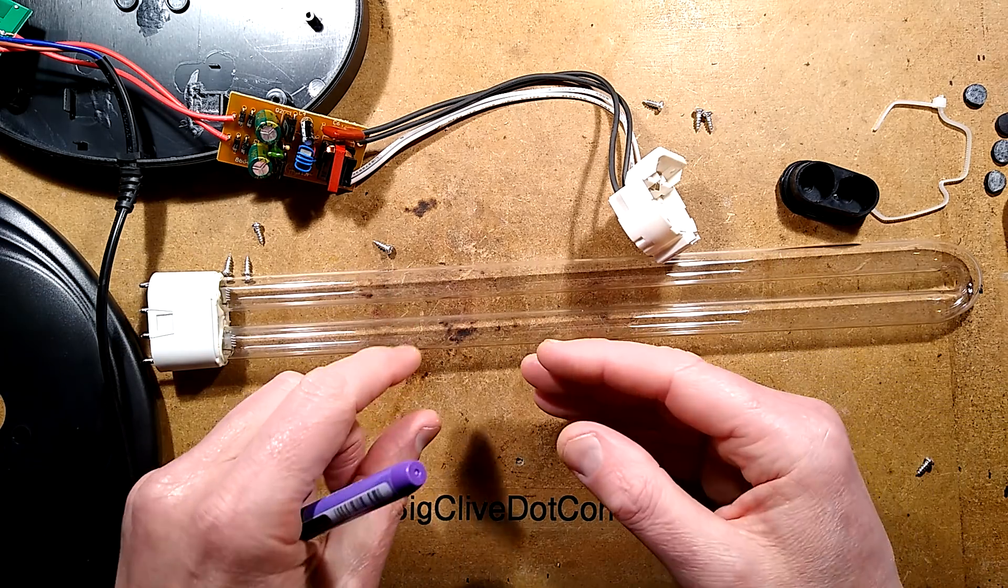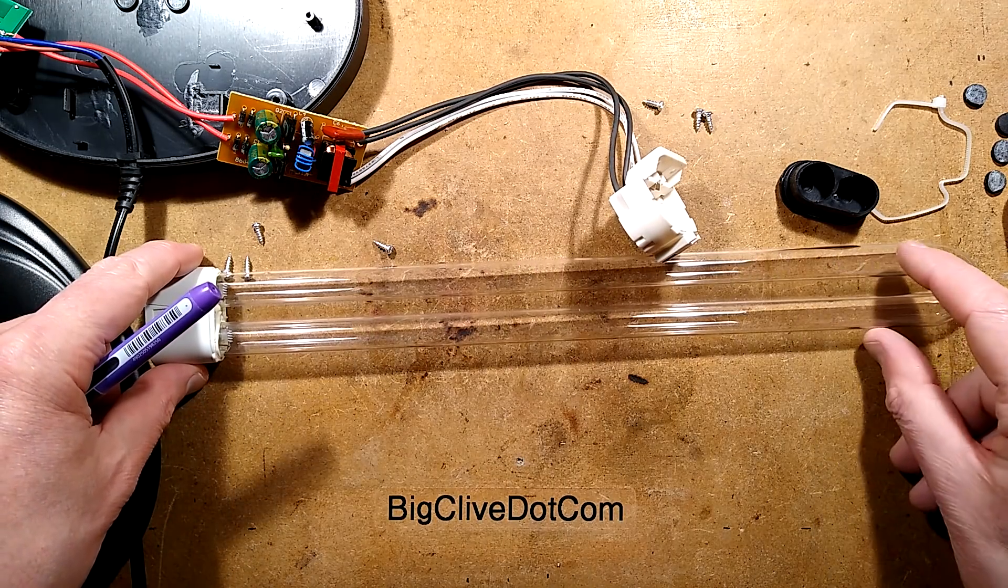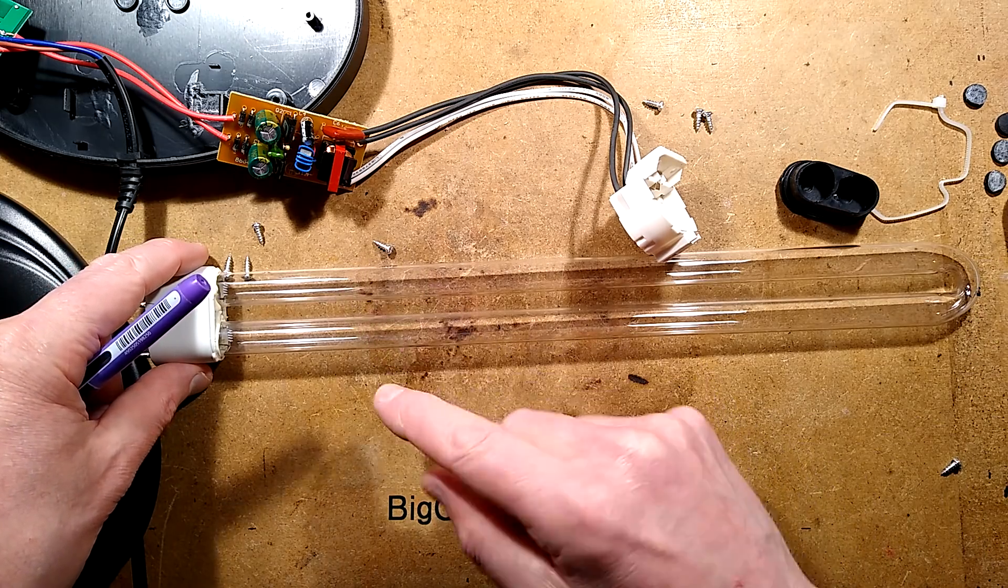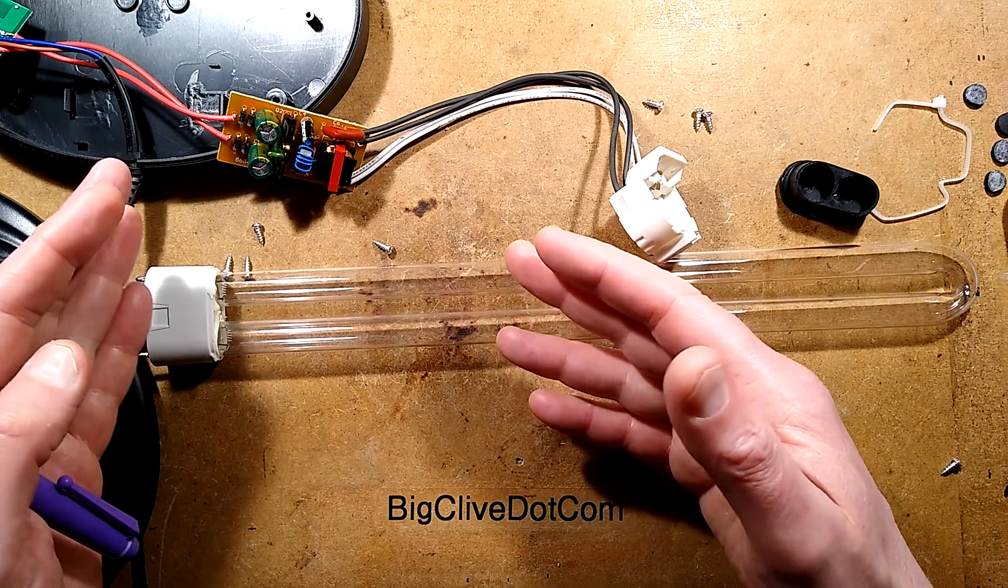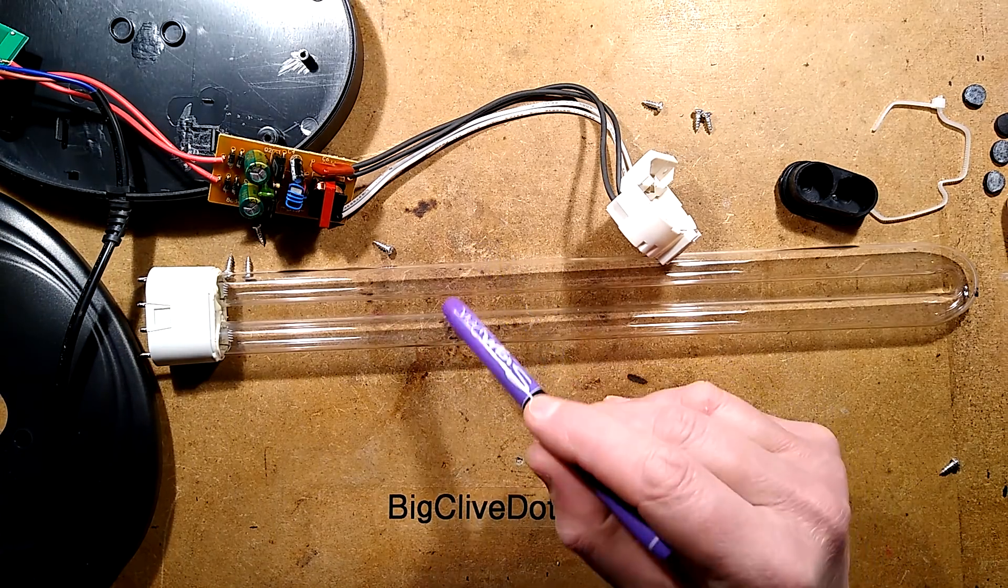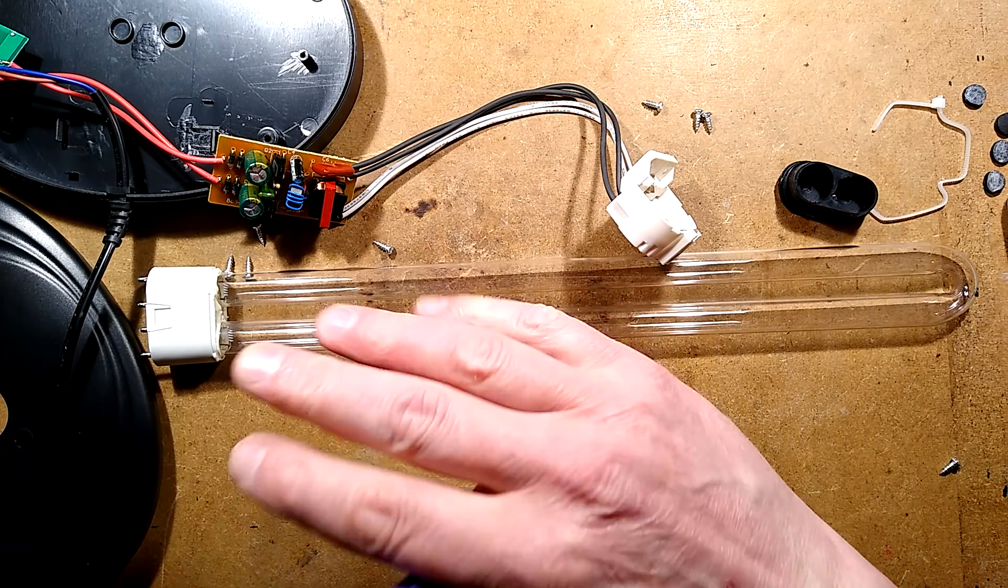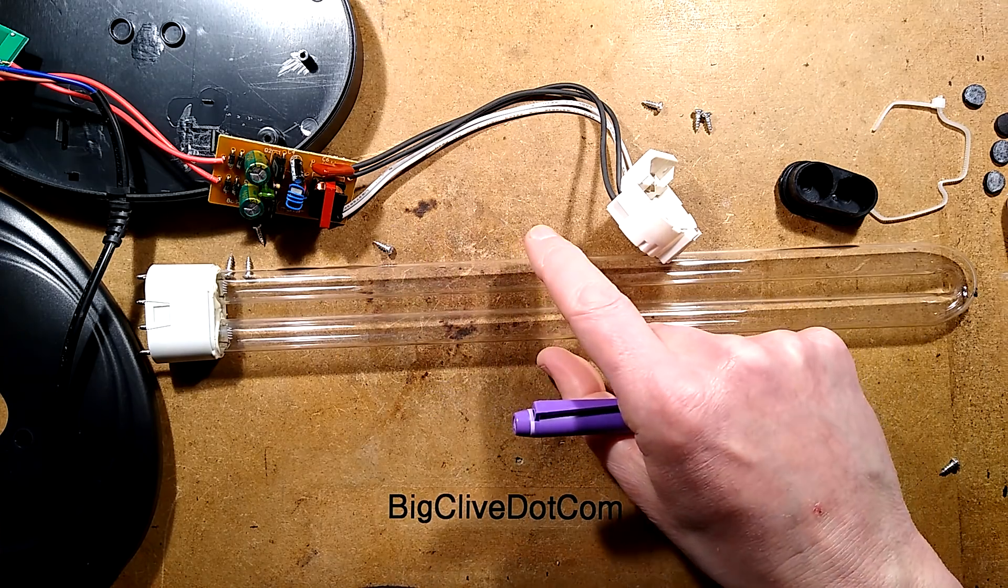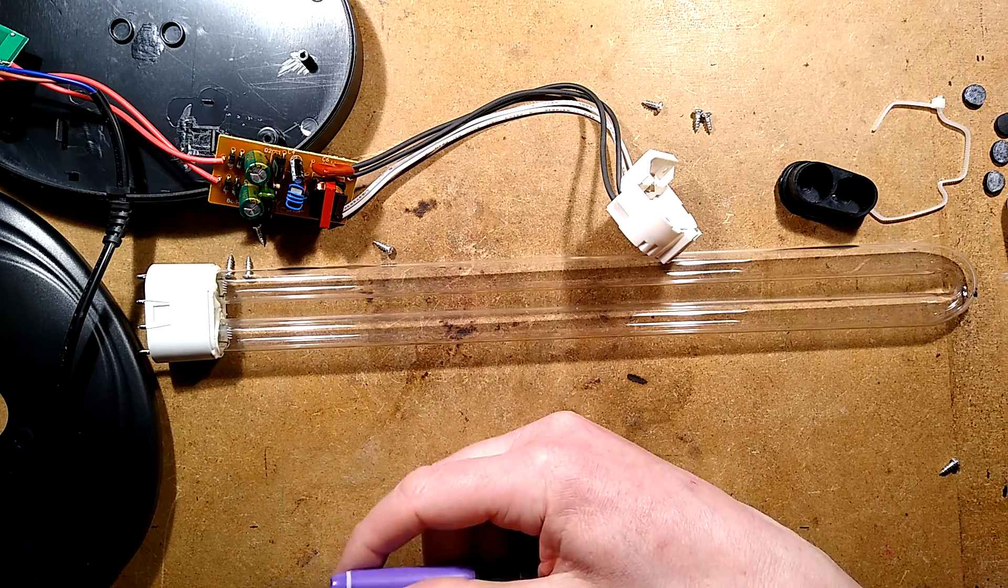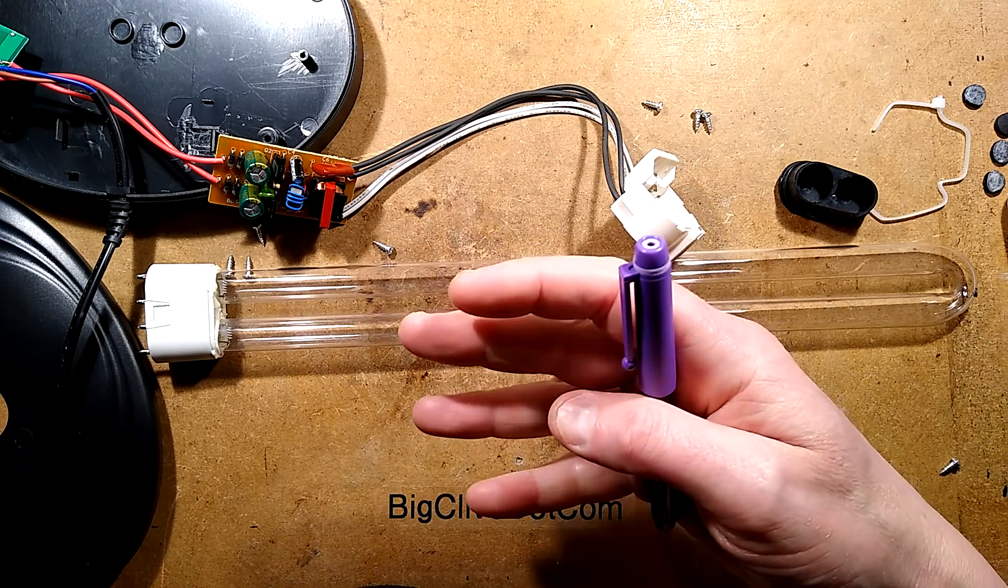One is in the UVA spectrum which makes things fluorescent but isn't really that harmful to humans. One is in the area that it has that germicidal effect. And one is in the area that it's germicidal and ozone generation, it's lower than about 200 nanometers when it starts actually splitting the oxygen bonds apart. And that's how it creates ozone in the air. You do get tubes that filter out the shortest wavelength which is the one that creates ozone. So you do actually get germicidal tubes that don't create ozone, but to me I think in this application they've used the basic one.